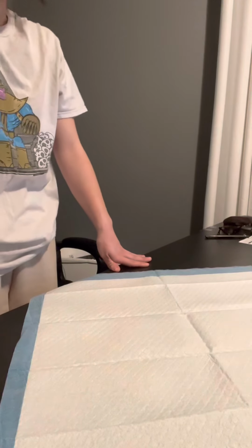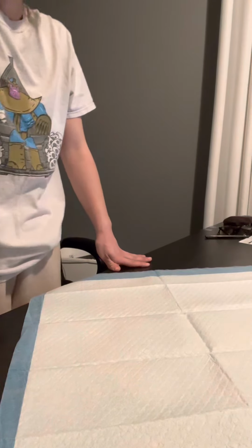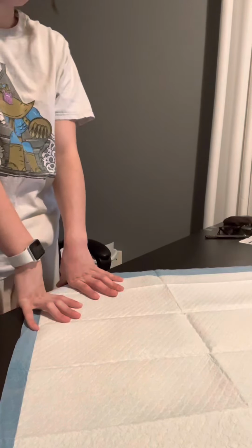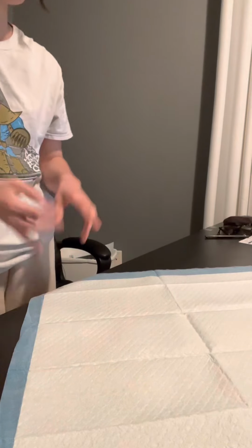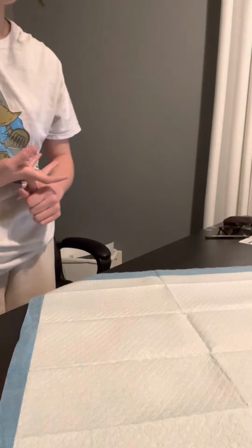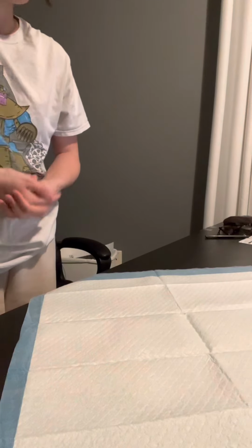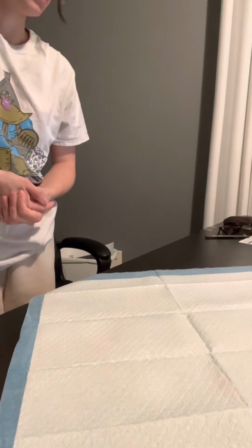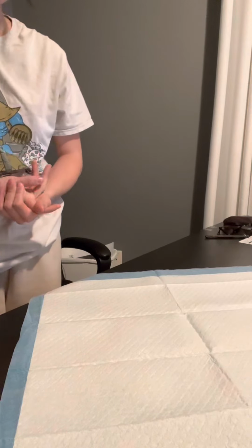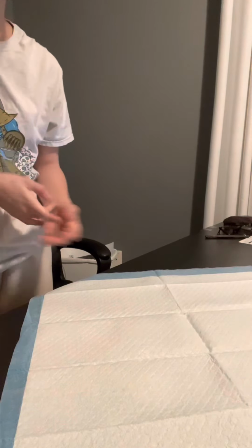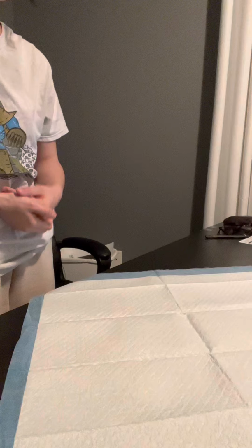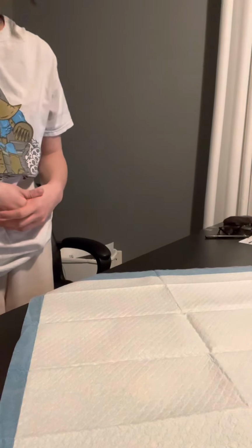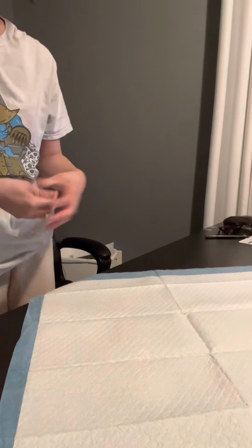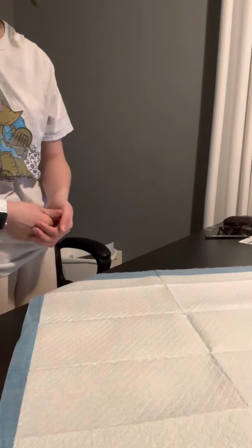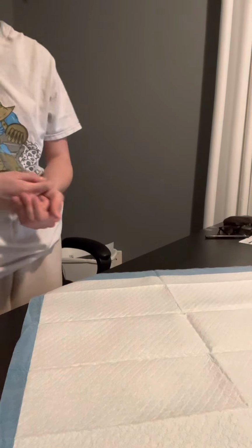When we're wrapping medical devices using this method, we are selecting the packaging material on a couple of factors. We want to look for the size, weight, and shape of the item being packaged, the method of sterilization, and the use of the item being sterilized. It's important that we look for these factors because if the wrapper is too big, it could, for example, inhibit the penetration. And if the wrapper is too small, it could result in too tight a wrap job. This could damage items due to overcrowding.